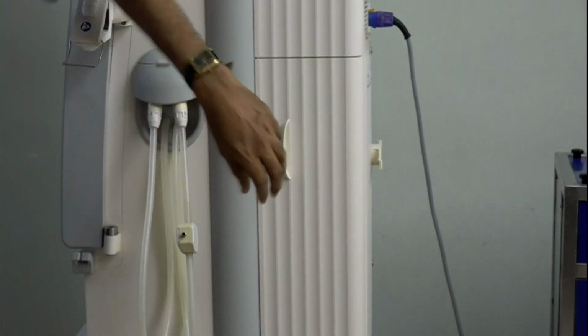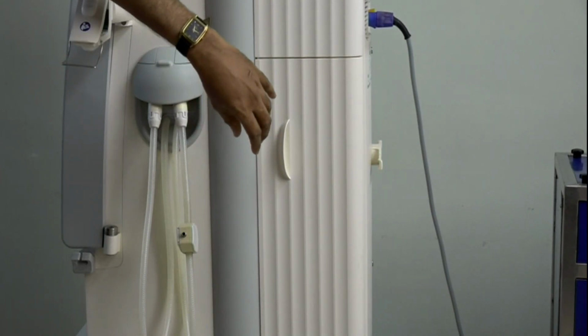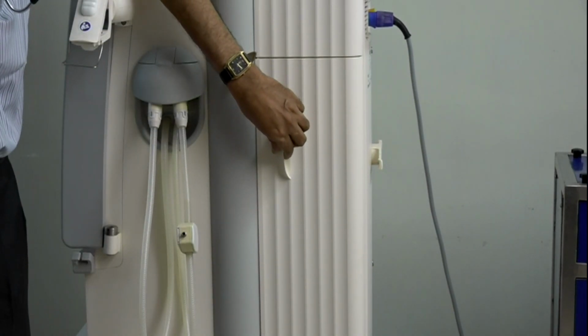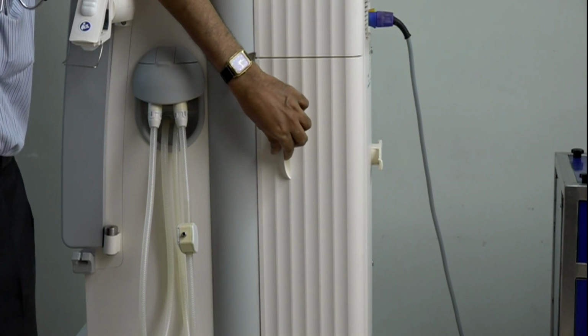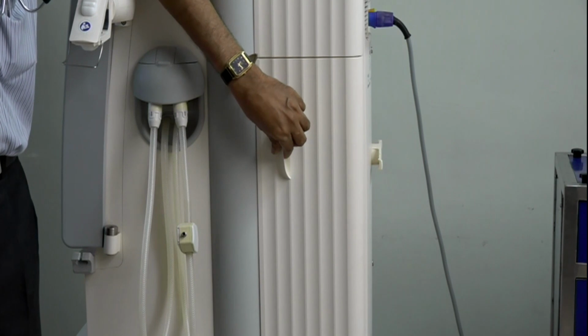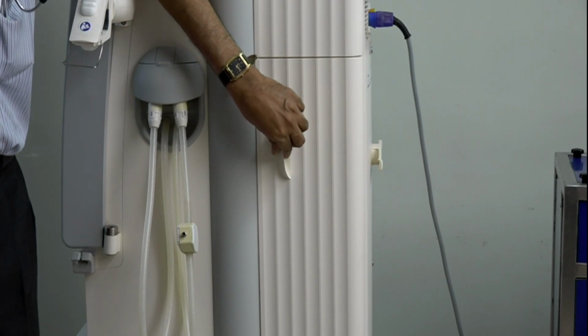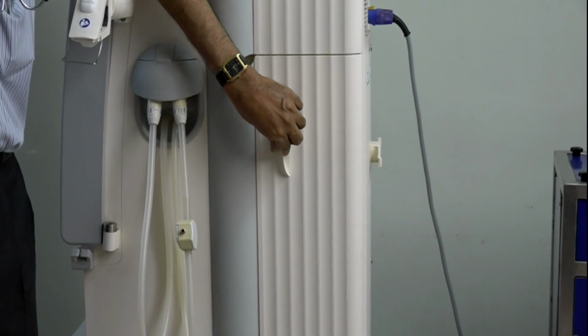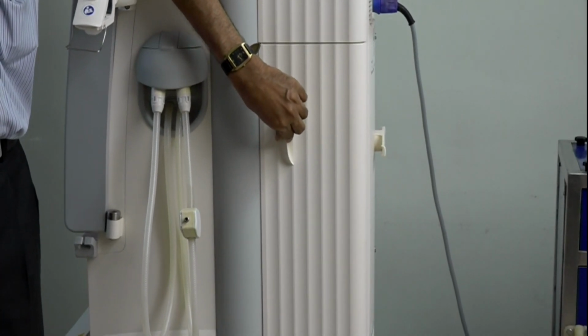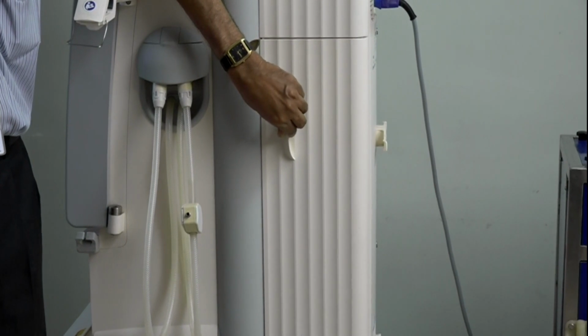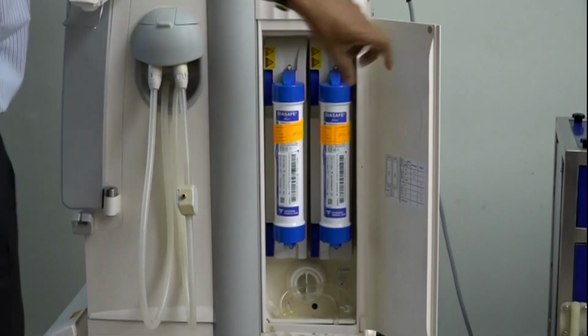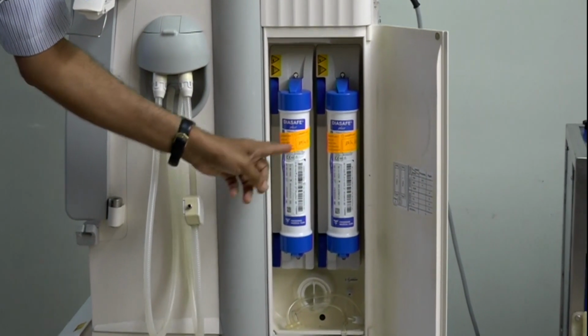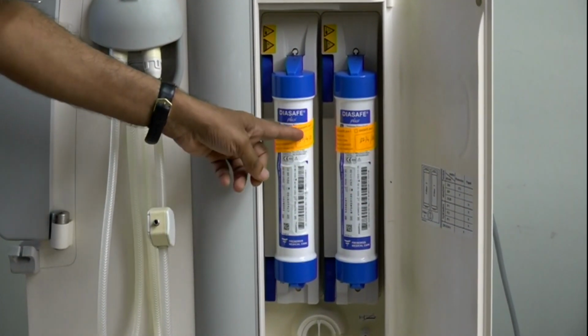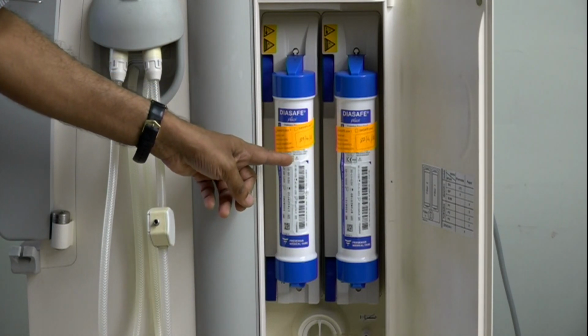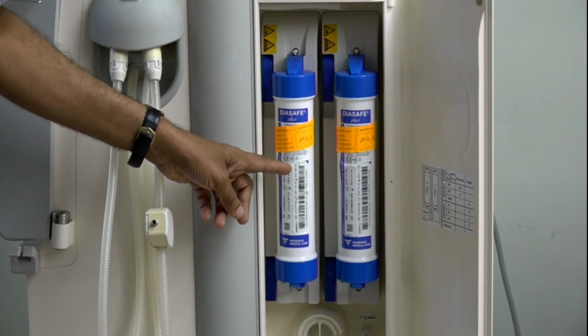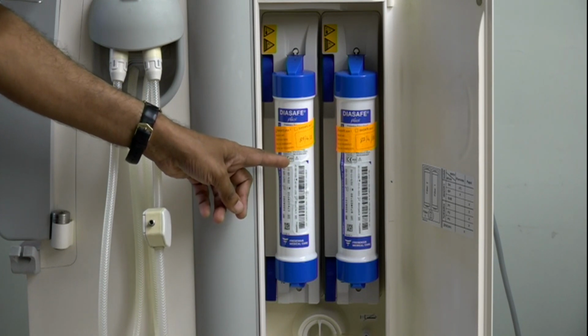Finally, we need a machine that is capable of producing a sterile ultra pure fluid which has a bacterial count of less than 1 in 1,000 liters and an endotoxin level of 0.03 endotoxin units per ml or less. This is done by machines like the Gambro AK200 Ultra and the Fresenius 5008 with the help of cold sterilization. That is, the dialysate fluid is sequentially passed through 2 ultra filters. In the case of Fresenius, the Diasafe Plus, each of which produces a 2 log reduction in bacteria and a 10 times reduction in endotoxin.